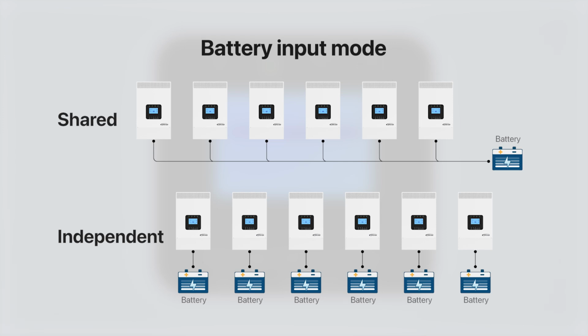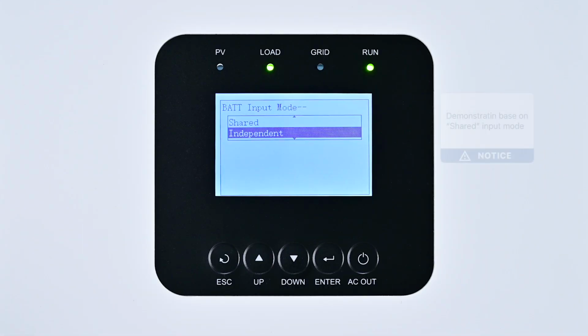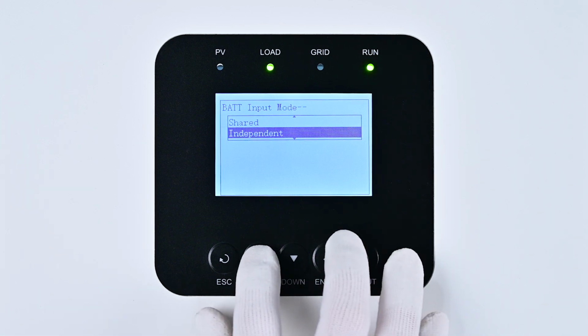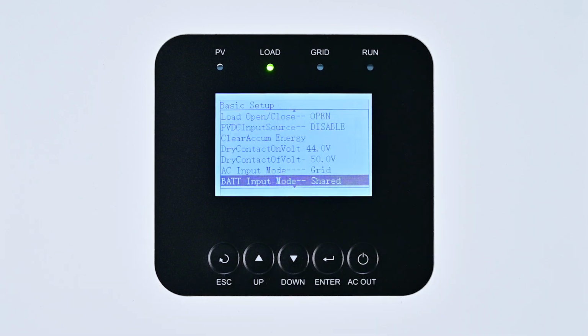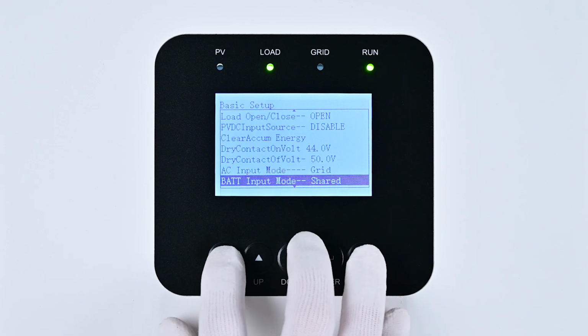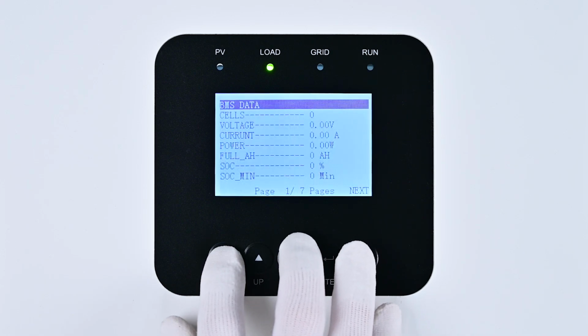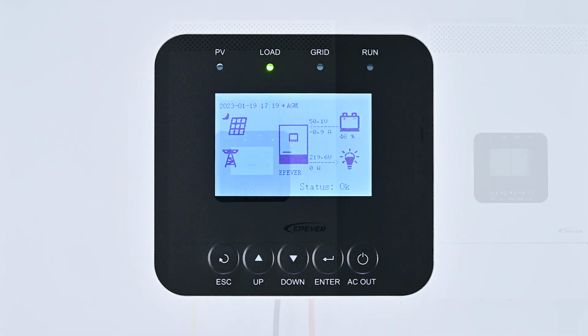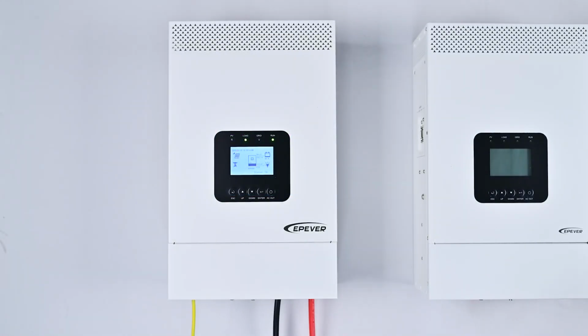Considering cost-effectiveness and ease of use, we recommend the shared input mode. Additionally, our demonstration will be based on using the shared input mode. Proceed to set the shared battery input mode by pressing the up key, navigating to shared, and then pressing enter to confirm. Subsequently, press ESC multiple times to exit the settings. After this, turn off the device. Wait for more than 10 seconds before turning the device back on.